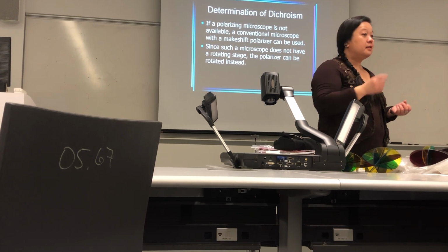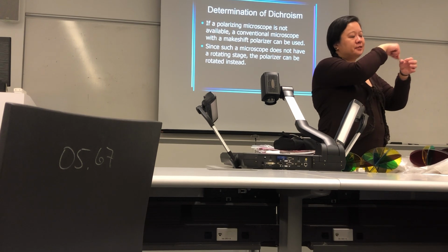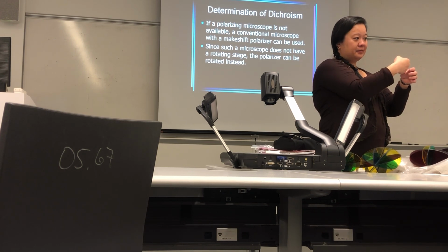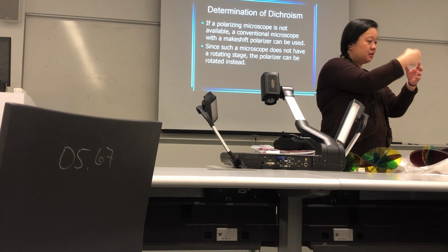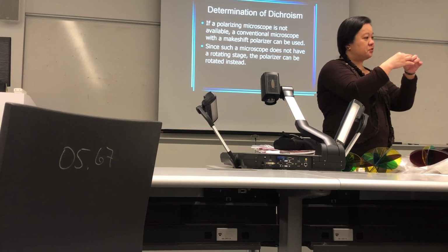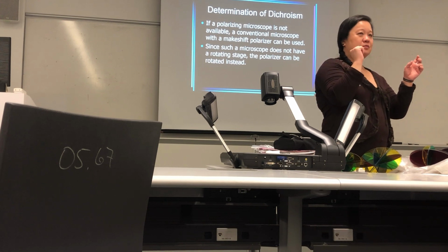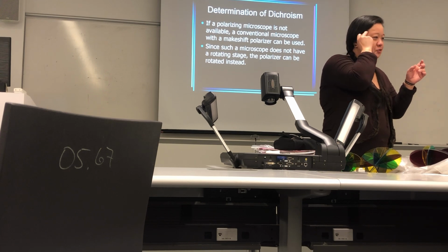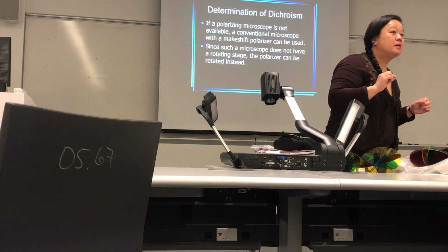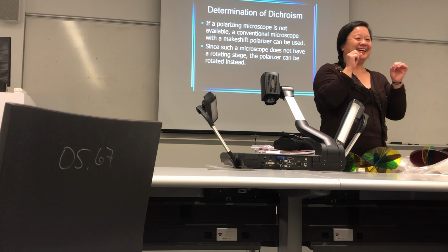Oh, okay. Yeah. Not only that, but remember when I showed you at my workshop last week, on the housing of the objective lens, it had the 40, which meant 40 times magnification. Underneath it, it had the 0.7, which was the numerical aperture. Underneath that, it had the 160 slash 0.15 or... I'm having a senior moment. 0.17? Yes, she's correct. Extra points for her.